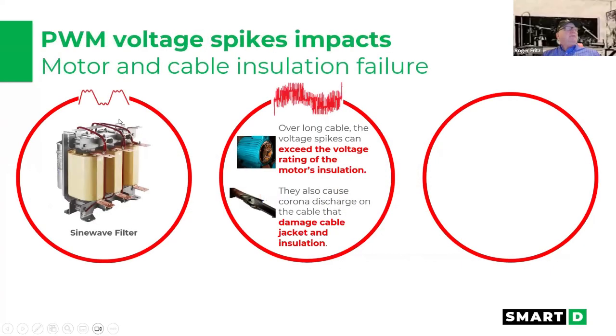So from that, on the typical IGBT drive, you put in these large sine wave filters on the output to get rid of that, and then still get some of the choppiness I showed you earlier, and you've got to have specialized cable to get rid of the corona discharges that happen on the cable over long leads.